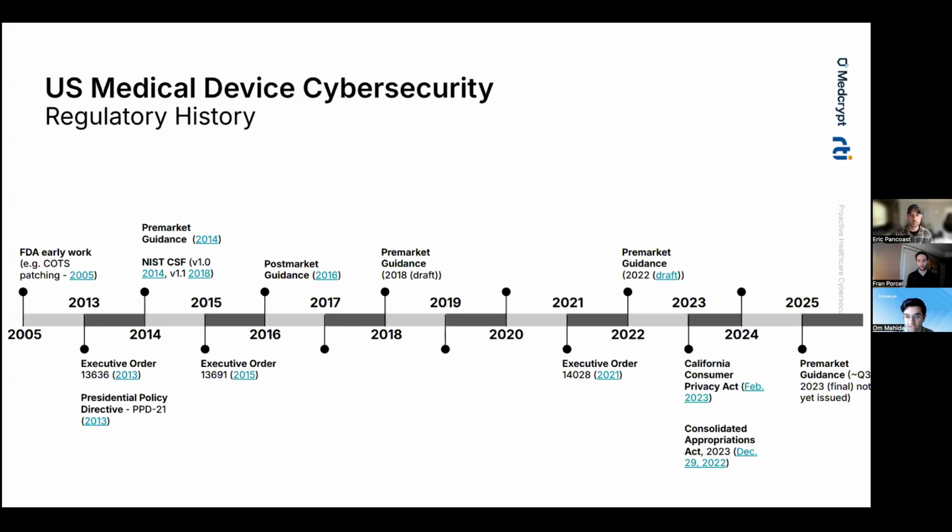We're seeing this a lot in the US and North America market between the FDA and Health Canada, but also in the EU through MDR and other regulatory agencies around the world. So the thing that's really changed in the past 5-10 years is that regulatory agencies, when they're reviewing your medical device for clinical functionality and safety, are also looking at the cybersecurity aspect of it.